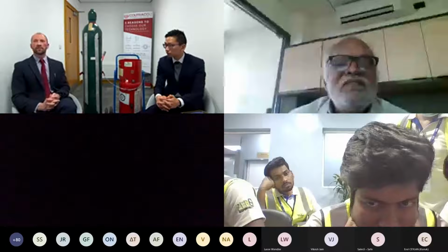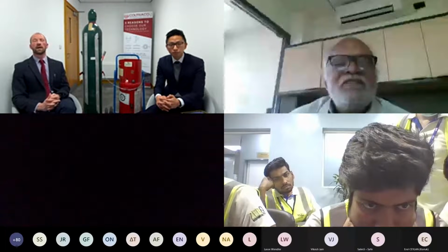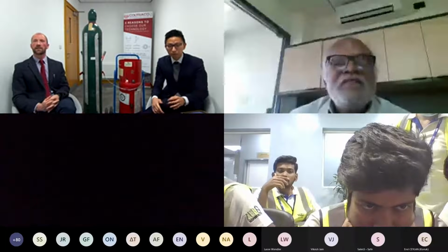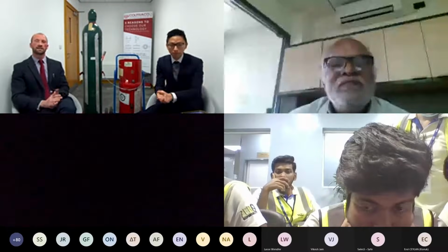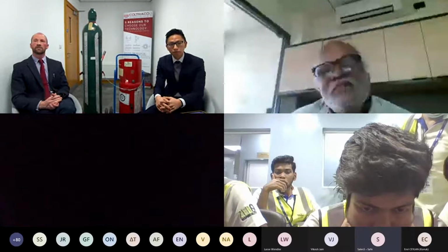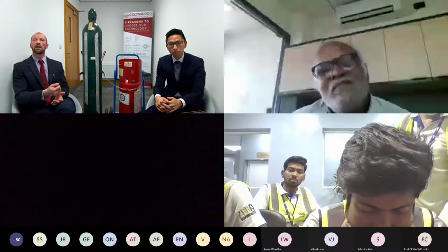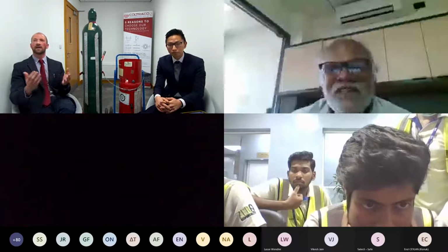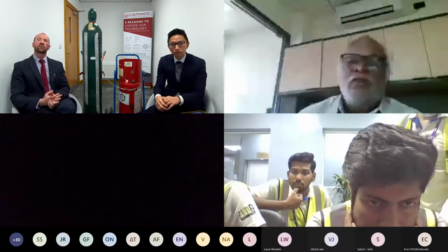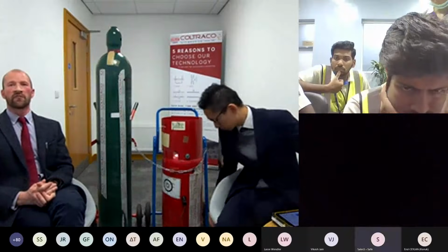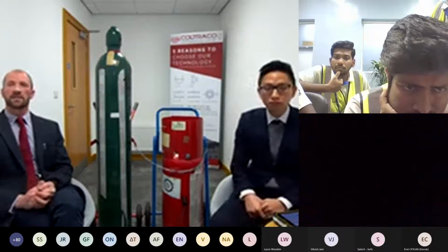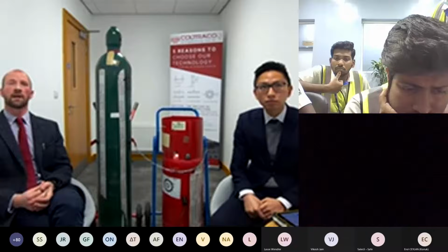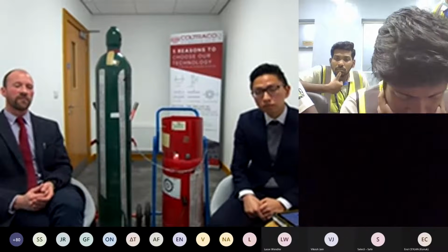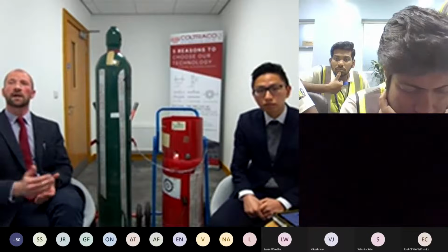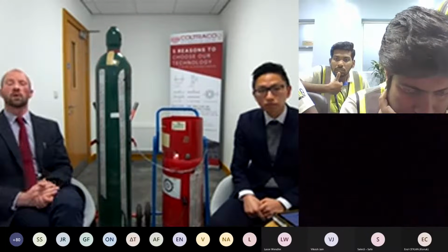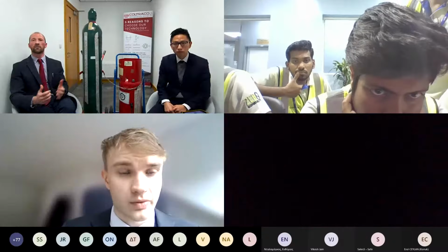So there are two major differences. One difference that you identified is that the unit will now tell you if you're in the gas or the liquid section after you calibrate the unit to that particular cylinder. But also, as you noted on the previous units, you calibrate to a specific cylinder in the area where you find the high readings. In this case, we now have 3 cal modes. Through extensive data collection and testing on a large variety of cylinders, we've managed to adjust our calibration algorithms, and we've found that these additional calibration modes give greater usability and greater flexibility when testing a larger range of cylinders.